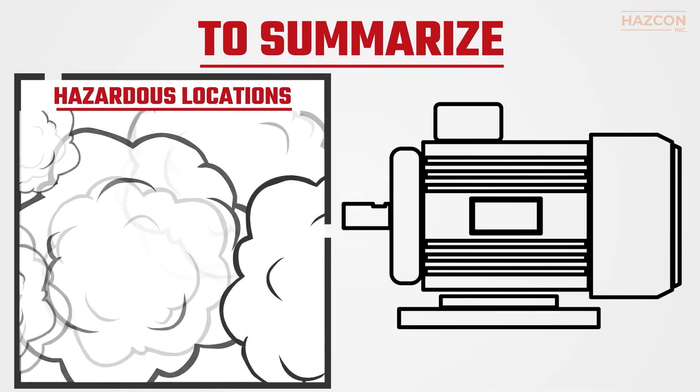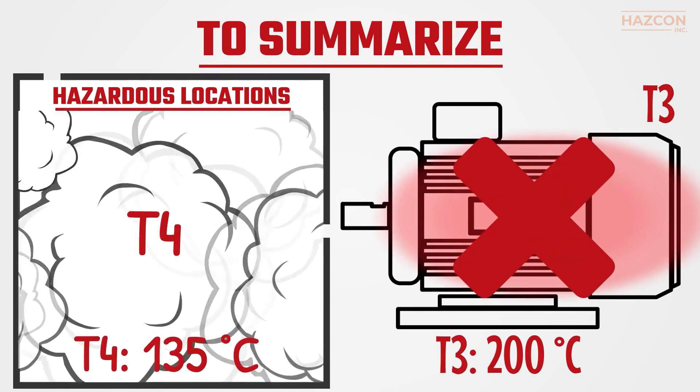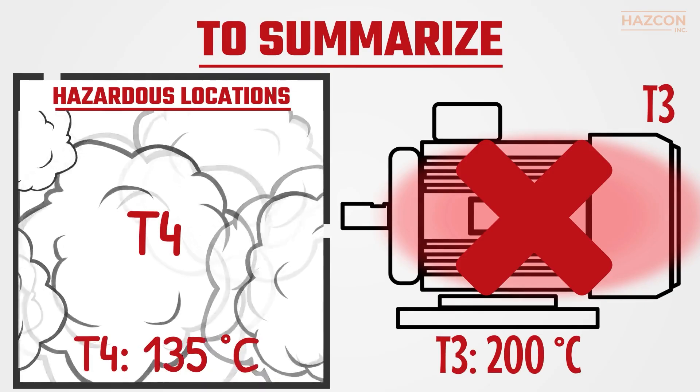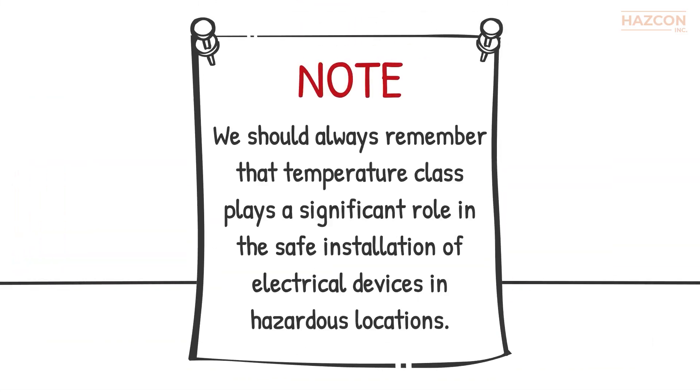But if a hazardous location application requires a T4 rated device, a T3 rated product will not be suitable. We should always remember that temperature class plays a significant role in the safe installation of electrical devices in hazardous locations.